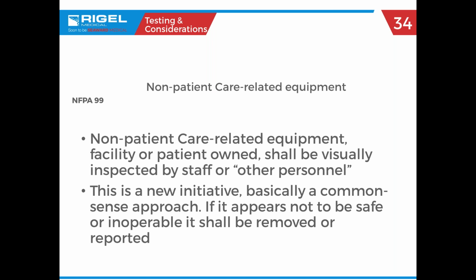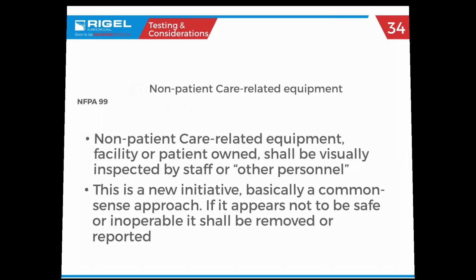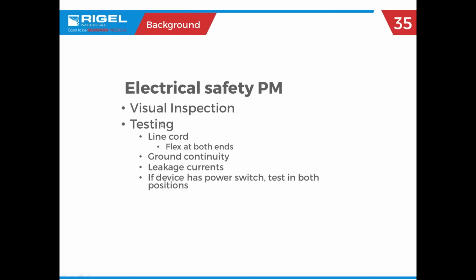So here are some more of the changes for the non-patient care related equipment. It basically states non-patient care related equipment, facility or patient owned, shall be visually inspected by a staff or personnel. This would be like your tablets or if you had a computer in there, things of that nature. And as long as everything looks good and it's intact, it's safe for use in the patient care areas. So that's a good thing. I knew they used to have to test even if you had a computer in there. And patients do not like having to live without their tablets and computers.